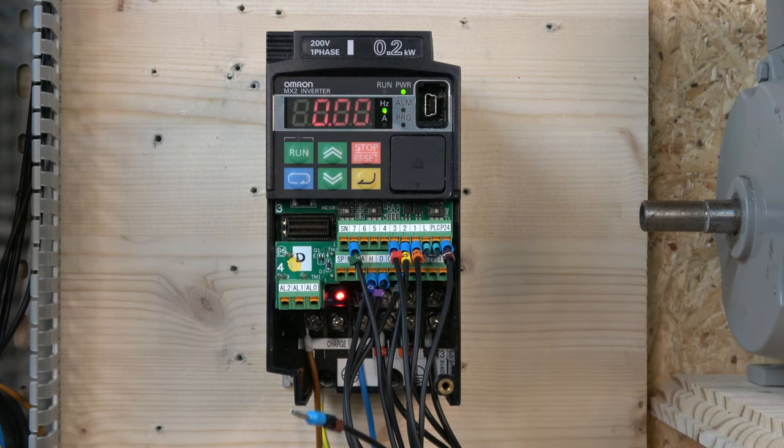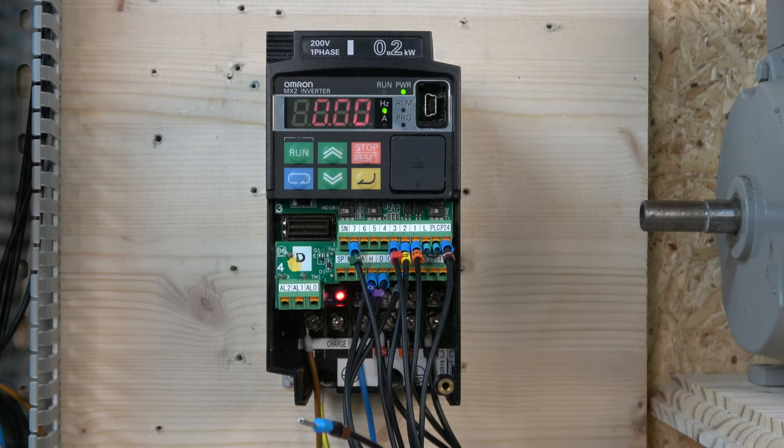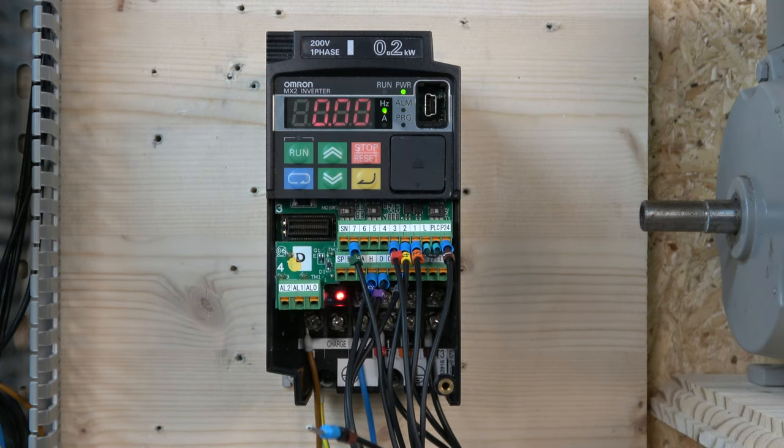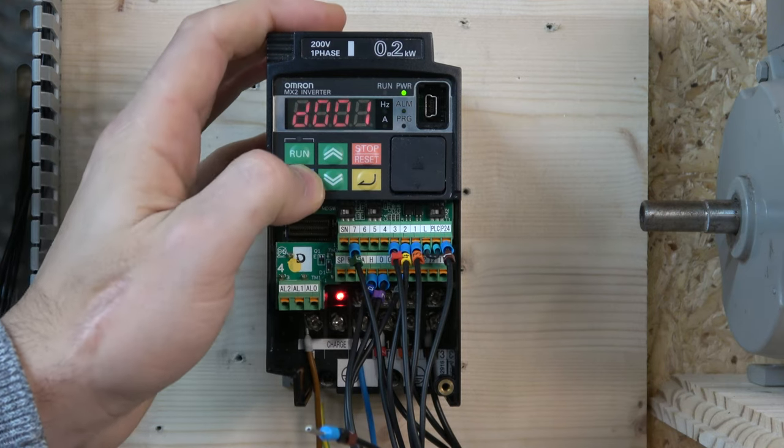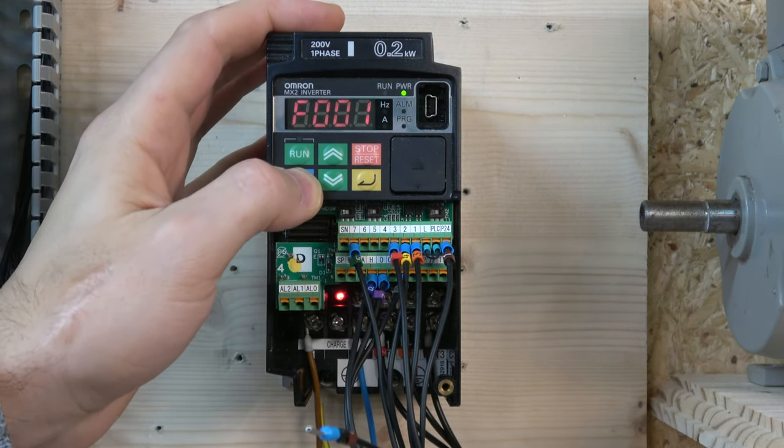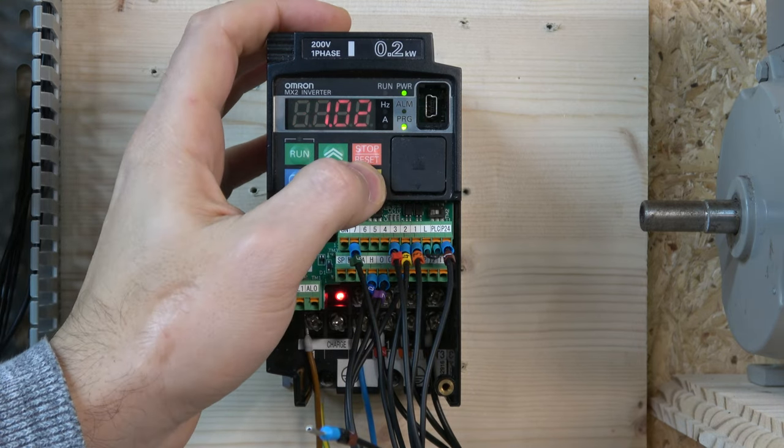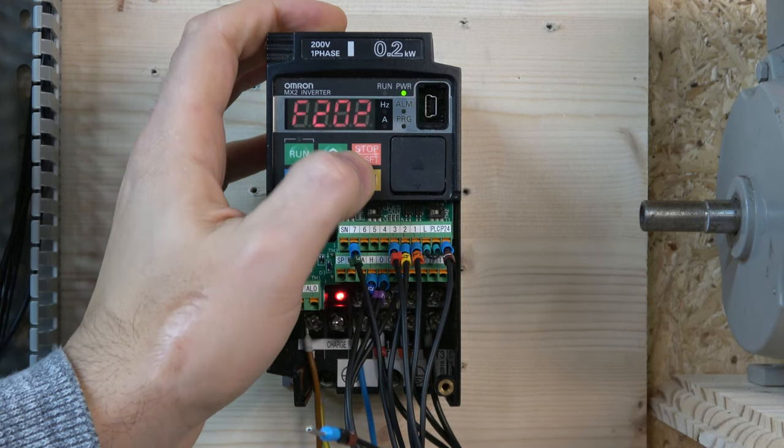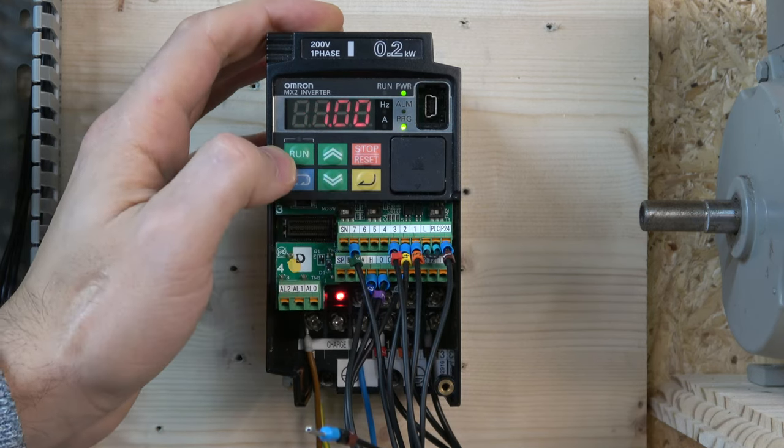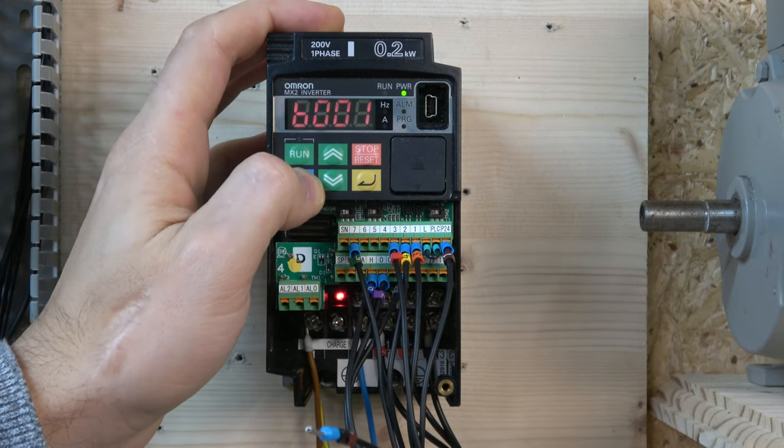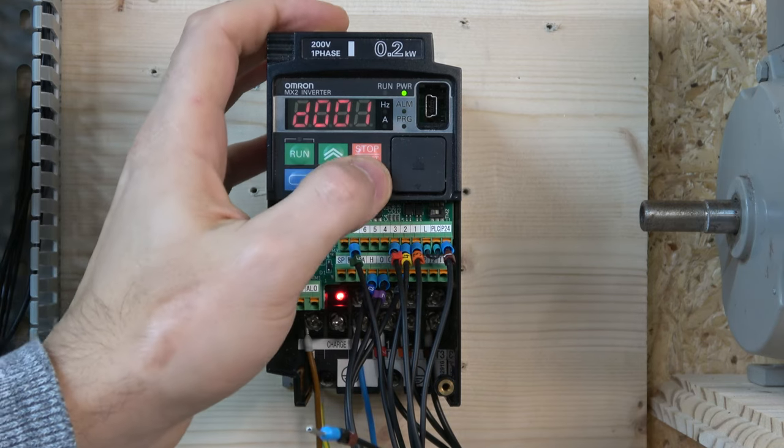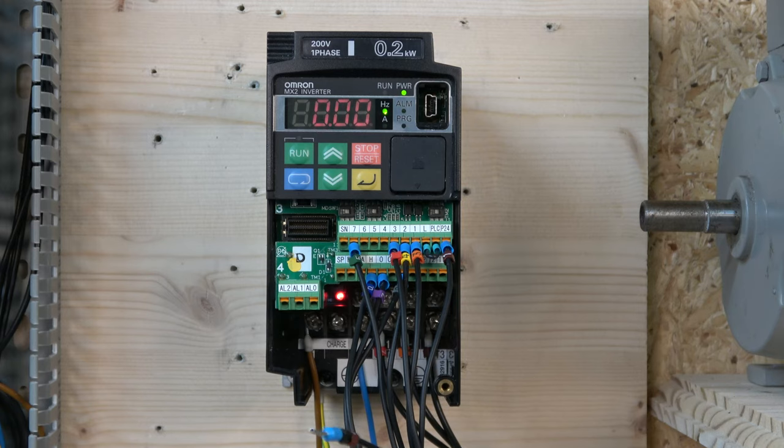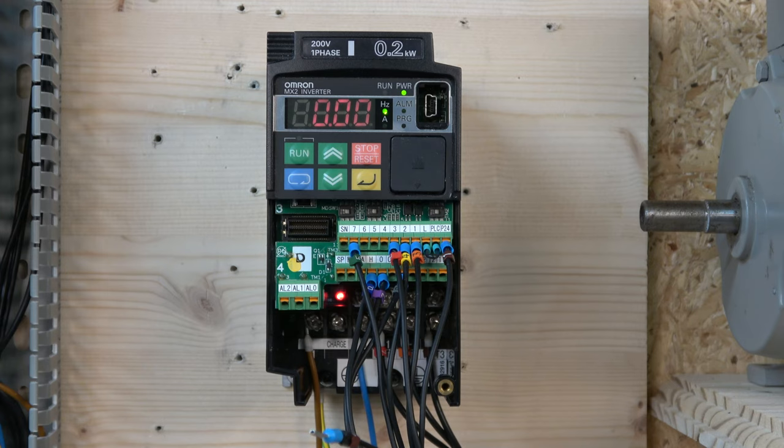I know it looks weird because it's got L up there as well. It's just a bottom L, O and H. That will be for your voltage, so that's where your potentiometer is going into it. When it comes down to jog button and things like accelerations, a lot of them you can do in F. Acceleration is F2 and F3 is going to be deceleration. You can see I set them both for a run.